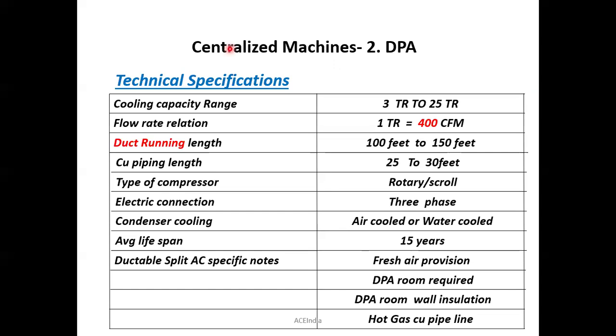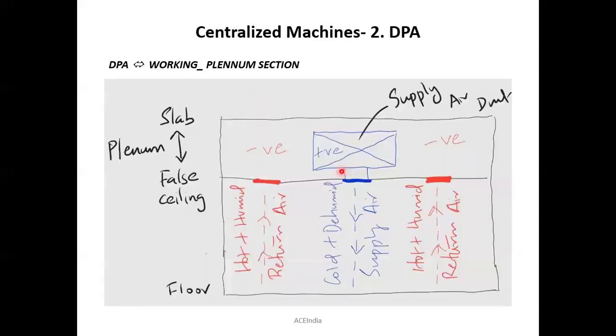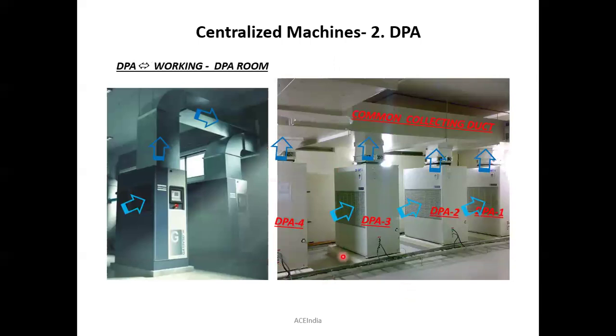Is the DPA room fully insulated, or a raised floor room? No, both need to be done. That is not only for the machine but also for the rooms. These connections are for the machine. But the wall insulation is for the noise which comes out from the continuous working of the machine. Gradually a noise will appear right inside the room. In order to prevent that noise from escaping from that room, we need mandatory acoustic insulation on the walls of that DPA room. Okay, clear?